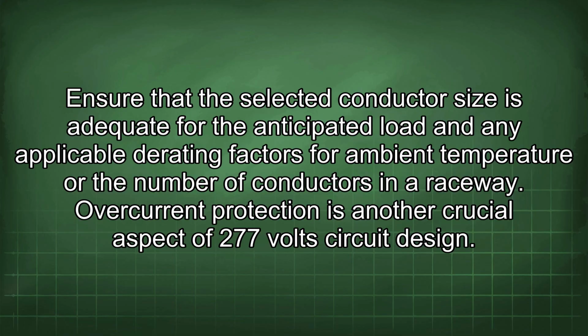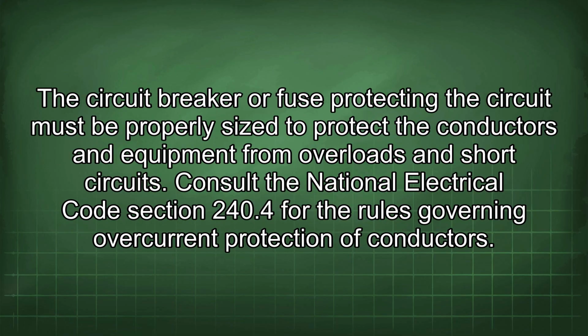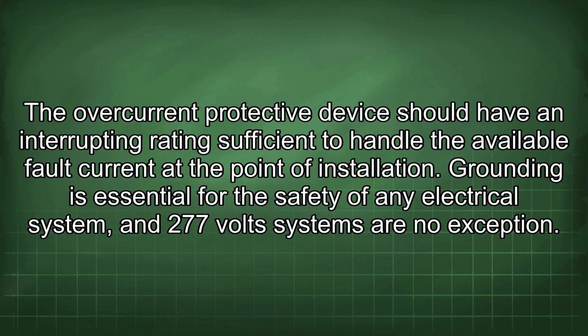Overcurrent protection is another crucial aspect of 277 volt circuit design. The circuit breaker or fuse protecting the circuit must be properly sized to protect the conductors and equipment from overloads and short circuits. Consult the National Electrical Code Section 240.4 for the rules governing overcurrent protection of conductors. The overcurrent protective device should have an interrupting rating sufficient to handle the available fault current at the point of installation. Grounding is essential for the safety of any electrical system, and 277 volt systems are no exception.